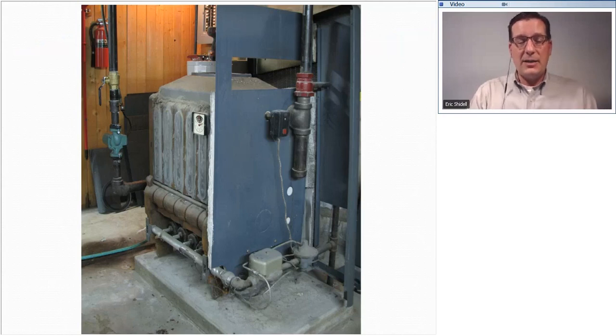Here's another cast iron sectional, probably manufactured in the 1960s or 1970s, and this one is on its way to be replaced. A couple of things to notice here. Notice the very old-fashioned gas train, but most importantly, look at the sections. There's an end section that comes down to the ground, which is part of the foot that the whole boiler sits on, and then on the other side, there's another one like that with a foot that the whole thing sits on. And in the middle are 1, 2, 3, 4, 5 sections all the same. So I've got one left-hand section, one right-hand section, and 5 middle sections that are all the same.